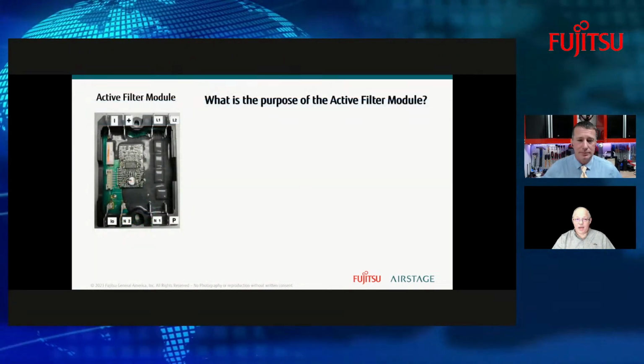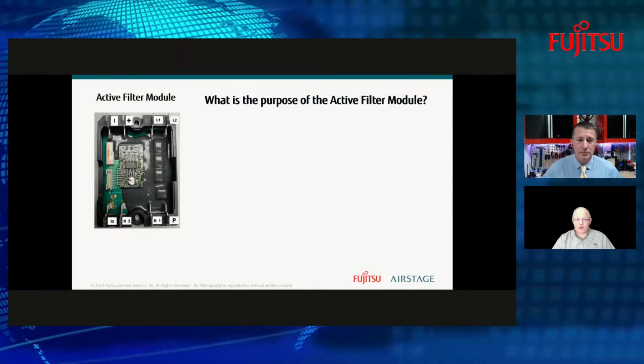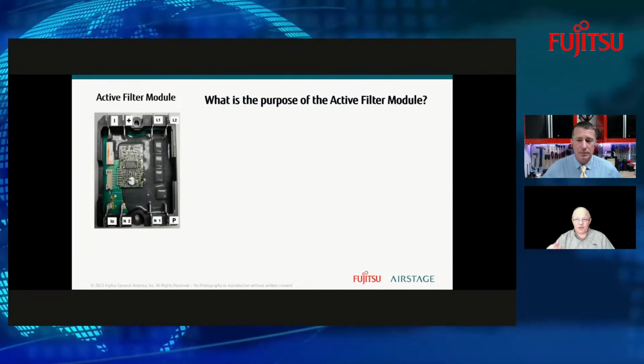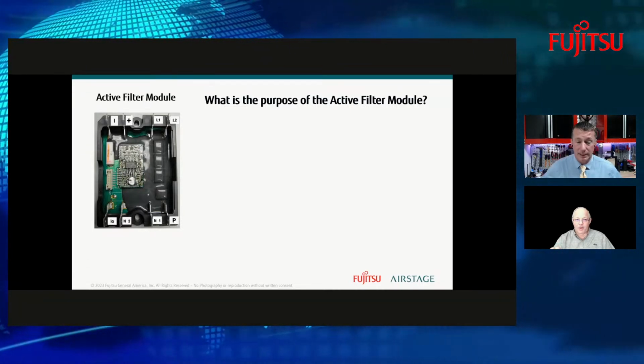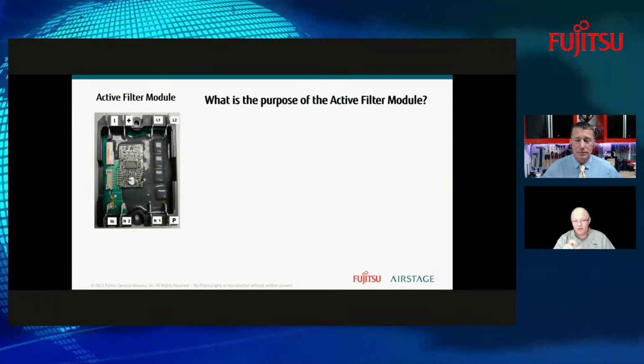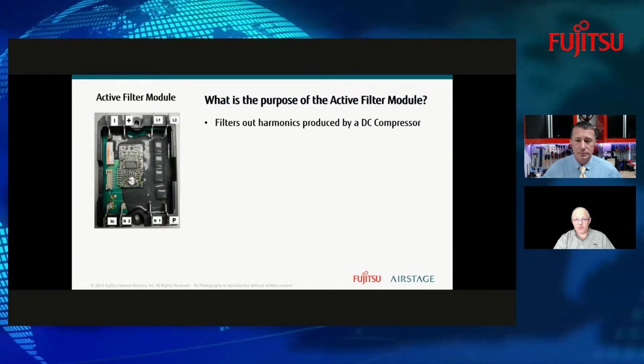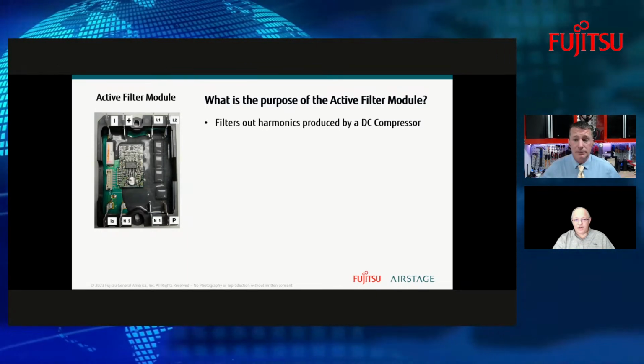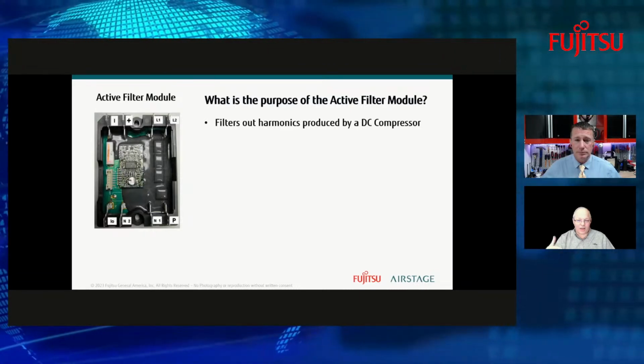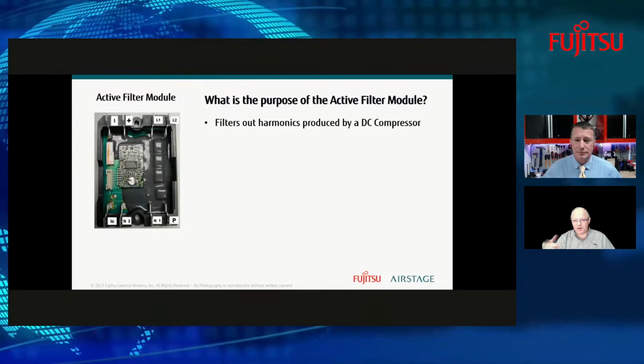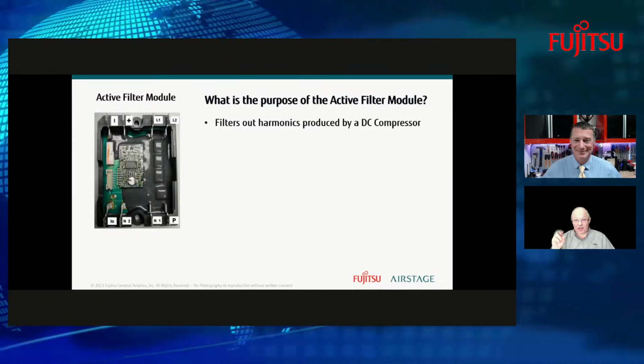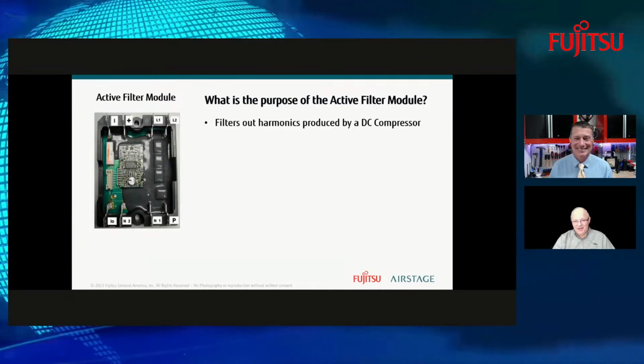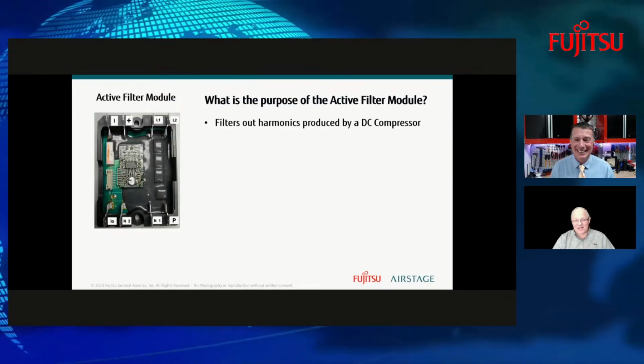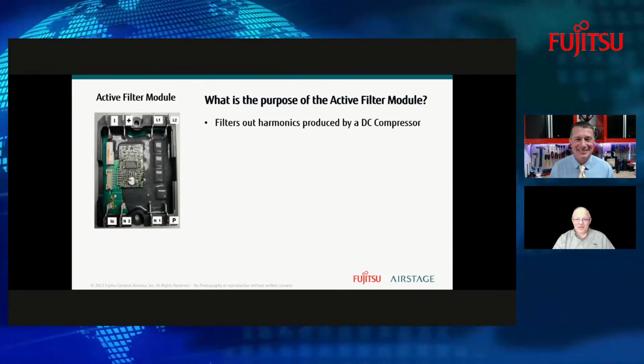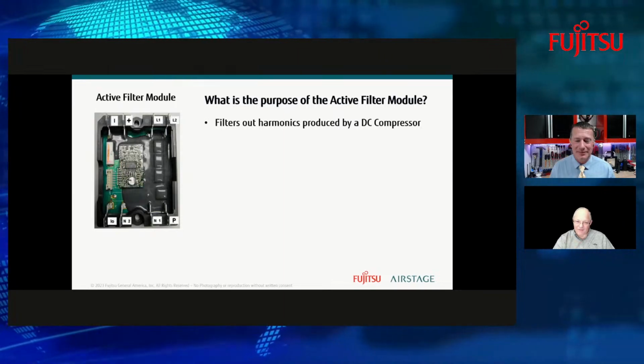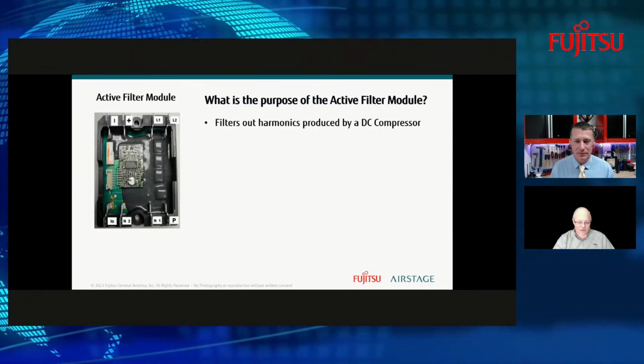All right. Now we're going to talk about the active filter module. This is a component that is pretty important as you get into the really super high SEER rated equipment. You won't necessarily see this module on every unit, but what it does is filter out the harmonics produced by the DC compressor. If you're older like I am, you probably remember the times when you used a hair dryer and you were watching the black and white TV and you'd see it. Absolutely. Well, that was what was causing it. There were harmonics coming back on the house. So this helps those harmonics not feed back on the house, which is caused by a DC compressor. Very important part.